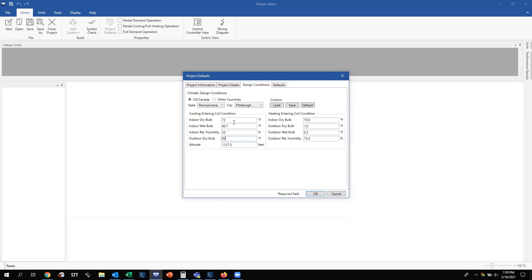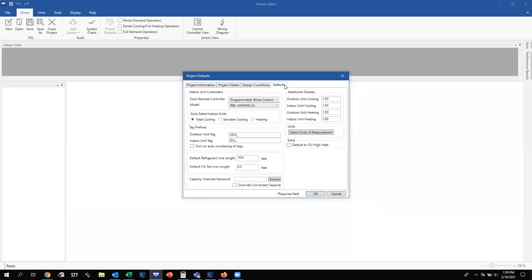We've got our design conditions entered — everything is good for cooling and heating. The last tab is Defaults, where you can set whether programmable wired controllers automatically populate for a zone remote controller with an indoor unit, or select the 24-volt interface as the default. I just leave it at the programmable wired controller. Auto Select Indoor Units lets you base selections on total cooling, sensible cooling, or a specific heating capacity. You can also change how units are labeled — by default it says outdoor unit, indoor unit — and you can change that.